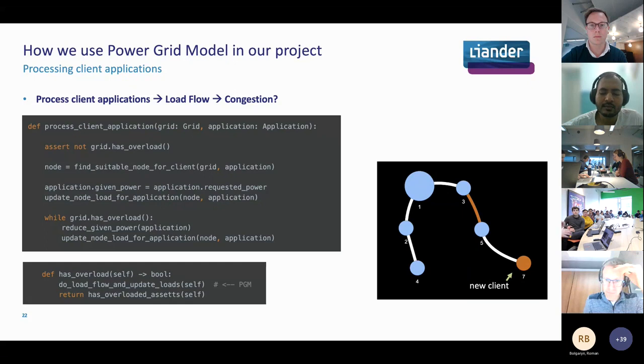So this is the process I was talking about. The load flow will return new loads, and then for example this node could become overloaded, and this line can also be overloaded. So we remove that requested power from the application, but we keep in mind that the original client wanted more power. So we have a transport limitation then.